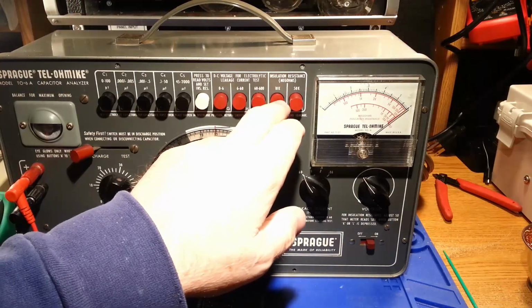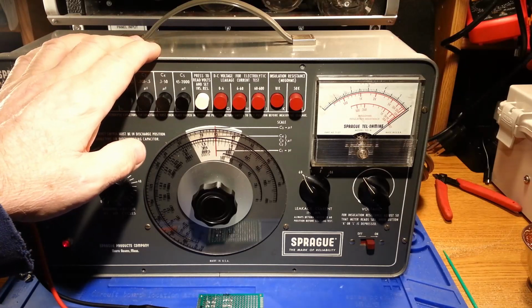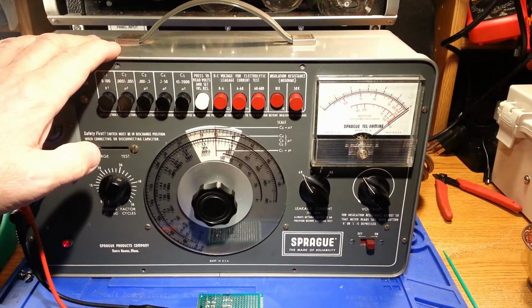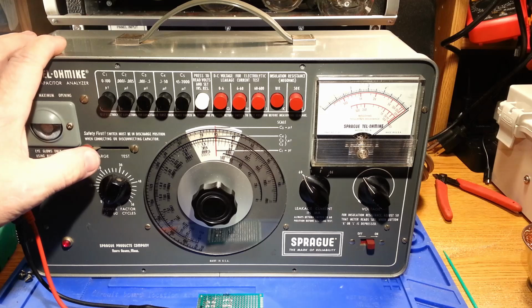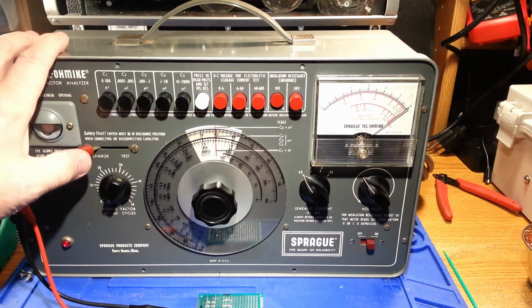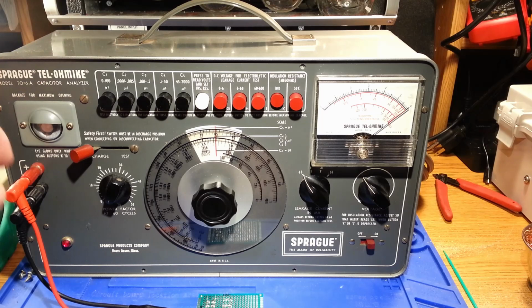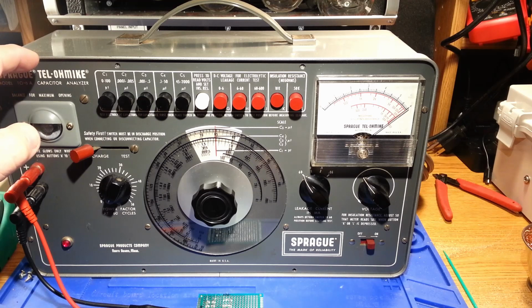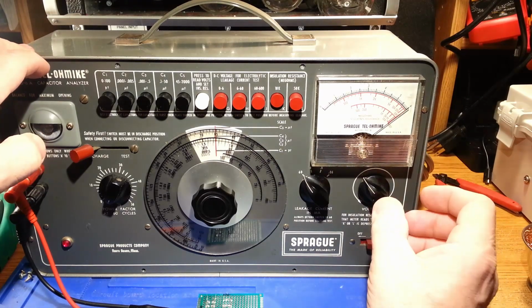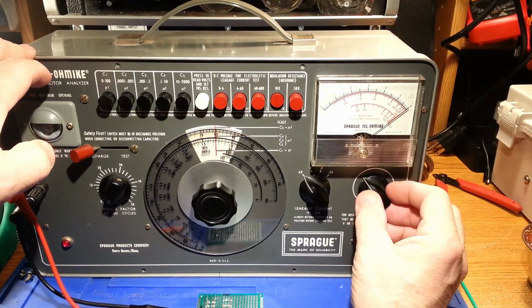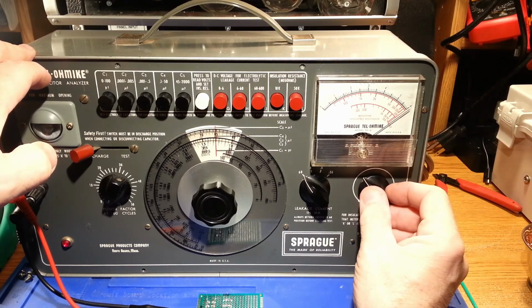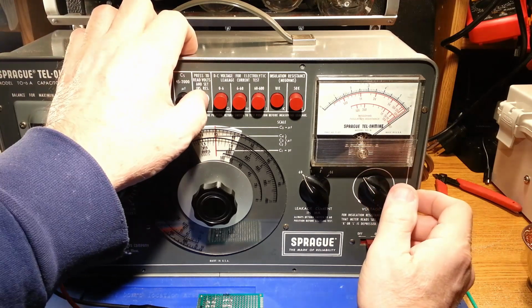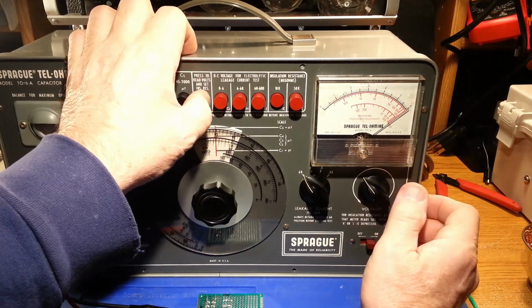There's a press-your-selection button for the 10K or the 50K megohm range, and at this point I've got leads connected. I have the capacitor lever in the discharge position, which means these leads are connected to a resistor and the internals are disconnected. You have to set the meter to a set point using the voltage knob, and the set insulation resistance button really doesn't do anything to the value.